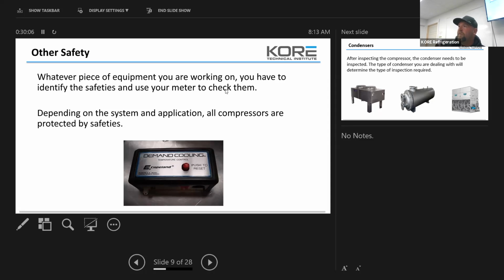Before you hit the magic button on an oil fail, I want you to gauge up to the compressor and the oil pump, and check your net oil pressure. If you're talking to me on the phone, or some of your lead technicians, and I ask about oil, I say, what's your net? I want you to look at the difference in pressure between your crankcase pressure and your oil pump pressure. It needs to be about 35 to 55 for a Copeland, where it's healthy. Somewhere in that range, and then I know our pump's working good, because that's the range for the sizes of compressors.